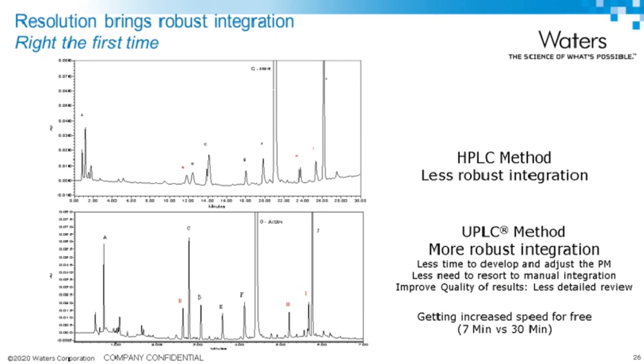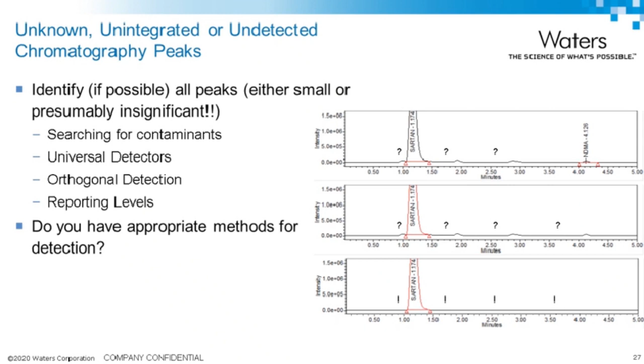As I mentioned, for our impurities, we have to be sure that we're looking for all the peaks. The small ones, the insignificant ones, are we sure we can ignore them? Is there anything in there that we should really investigate further? Maybe look at a different detector method, in case I can find something using a different orthogonal detection. What are the reporting levels? Why have some of those peaks not been integrated? Or are they just not available at the particular wavelength that I'm monitoring, and they may be seen at a different wavelength? Do we have the right method for detection? It's a question we need to go back to our impurities tests and examine their scientific fit-for-use purpose.